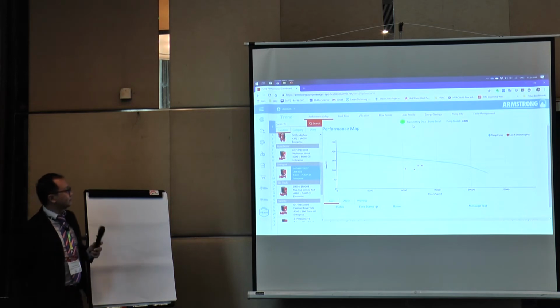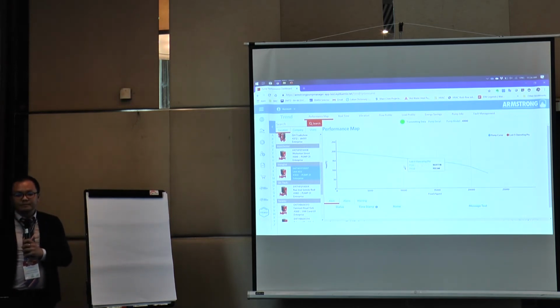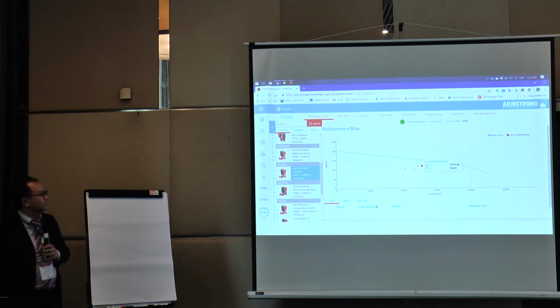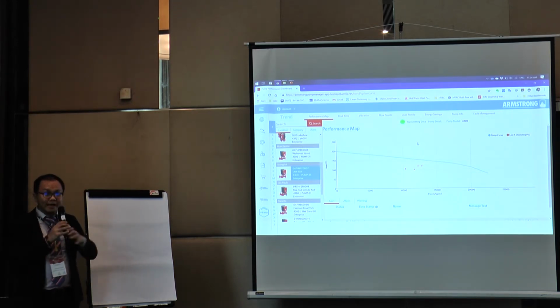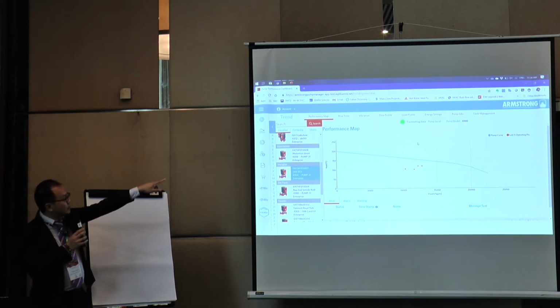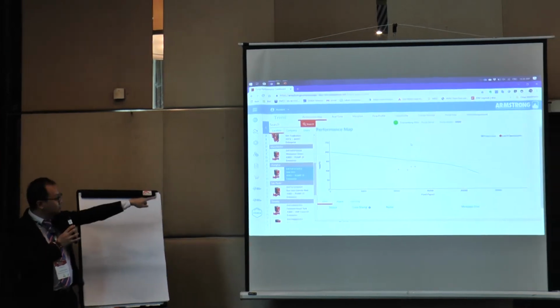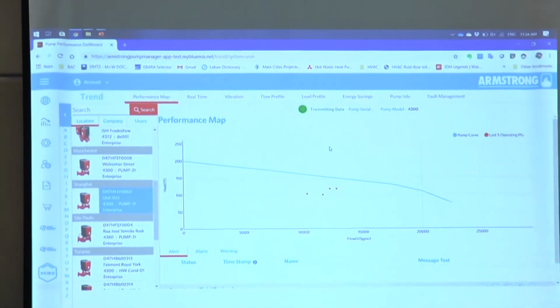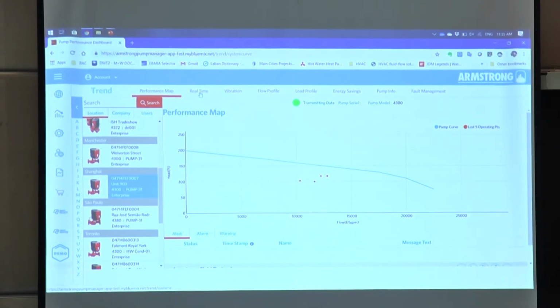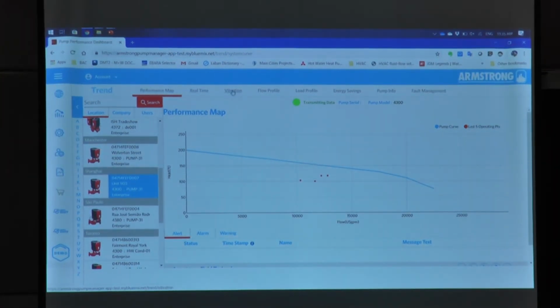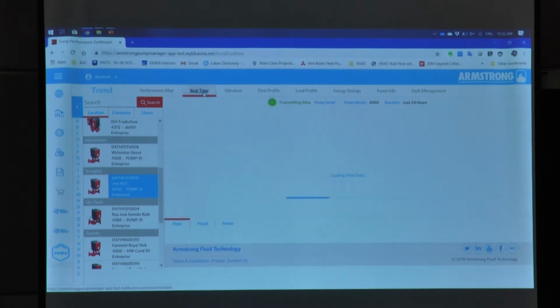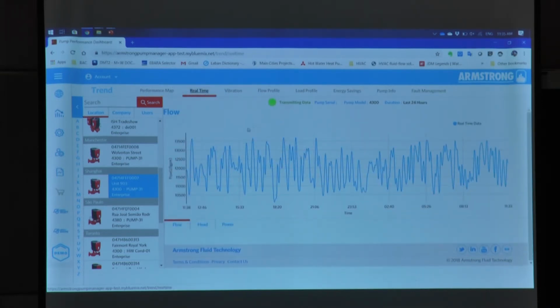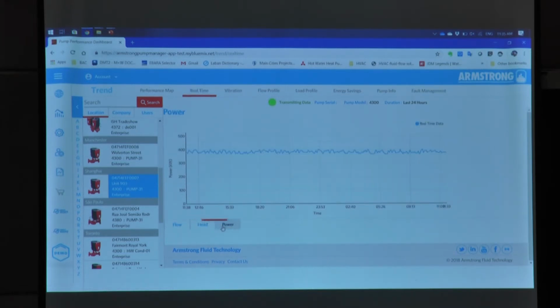Then you can see this is the status transmitting the data, and then we get the last data. So this is actually live data, real-time information, right? So that's why it says transmitting it. We actually connected to the pump directly in Shanghai to get this performance curve. Yeah, here has some tabs, the performance map, the real-time vibration, flow profile, load profile, and energy savings we can see here, real-time. Yeah, this is the real-time for the flow, and also head, powers you can choose. Yeah, we can try. Yeah, this is head and also the power.